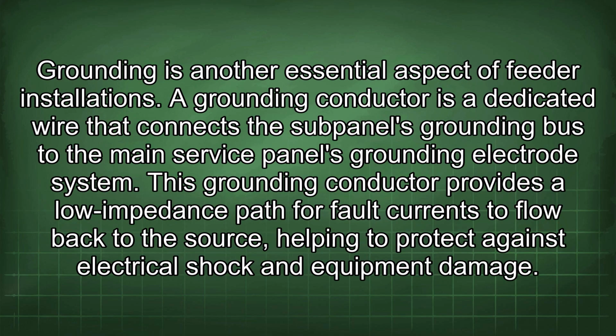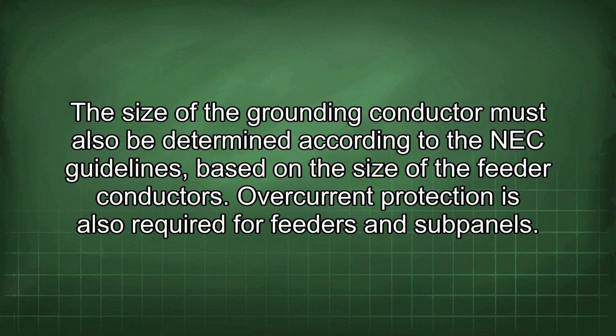Grounding is another essential aspect of feeder installations. A grounding conductor is a dedicated wire that connects the subpanel's grounding bus to the main service panel's grounding electrode system. This grounding conductor provides the low impedance path for fault currents to flow back to the source, helping to protect against electrical shock and equipment damage. The size of the grounding conductor must also be determined according to the NEC guidelines, based on the size of the feeder conductors.